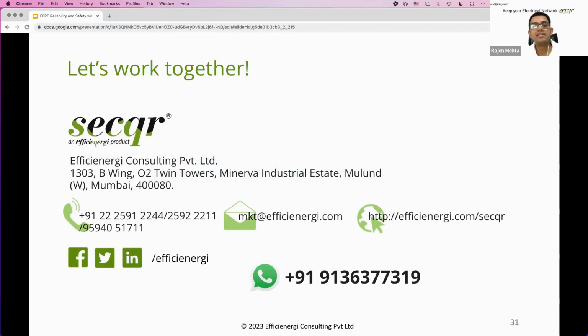There may be something in the chats. Okay, Farooqji asks in the chat: voltage flicker due to load is now restricted to plus or minus 1%, touch base needed in view of power quality. Sir, when you say that, for most of the loads I do agree that they are not exceeding those limits. It's only in the case of loads like induction and arc furnaces or some such highly fluctuating and variable loads. So VAR compensation is one of the easiest and most cost-effective ways to address these flickers, especially for these very fast acting loads. And obviously, if the starting of these loads can be through drives or soft starters and so on, that will also allow these rapid voltage changes to be addressed to a large extent.